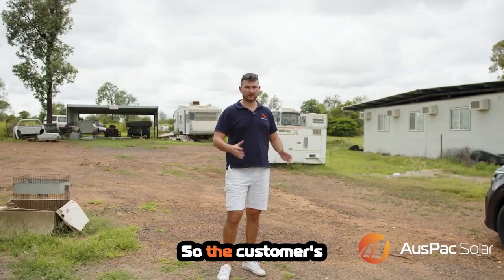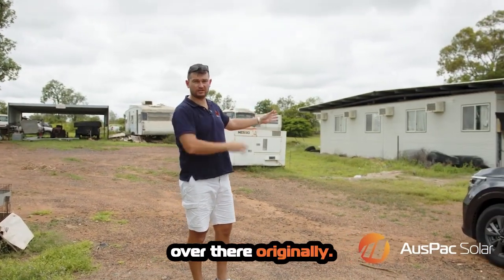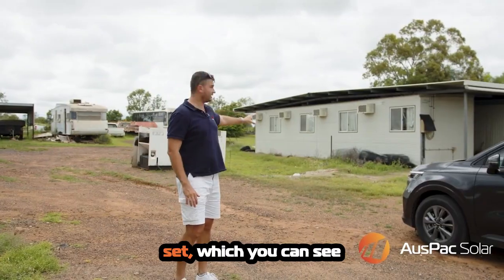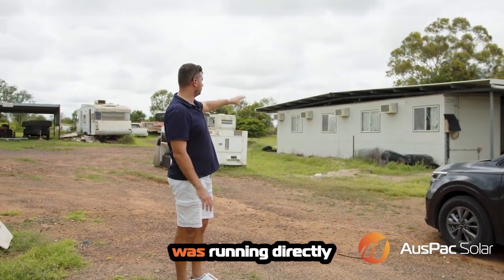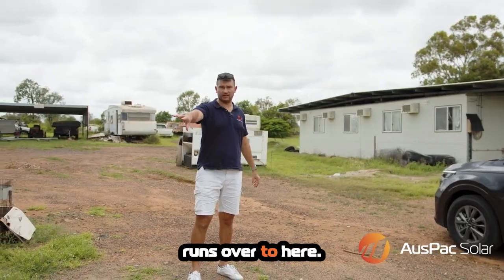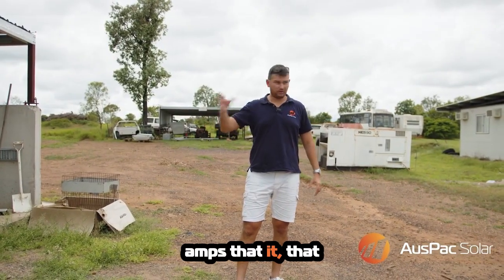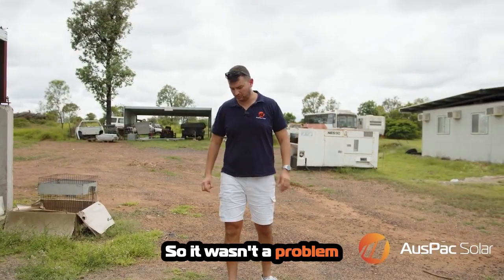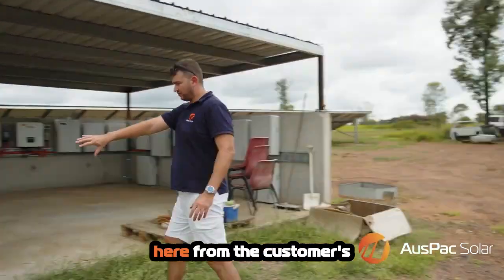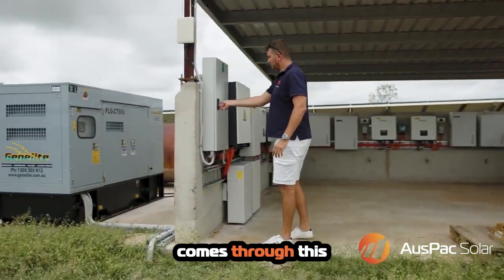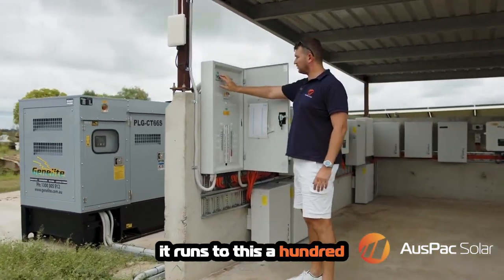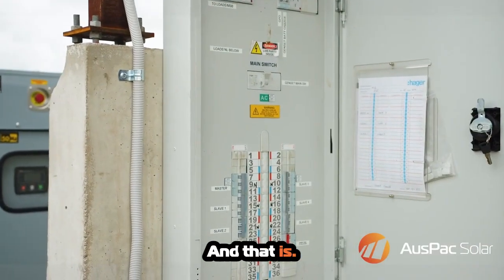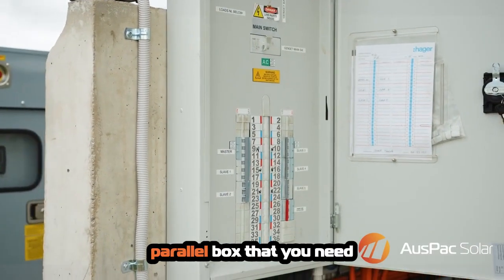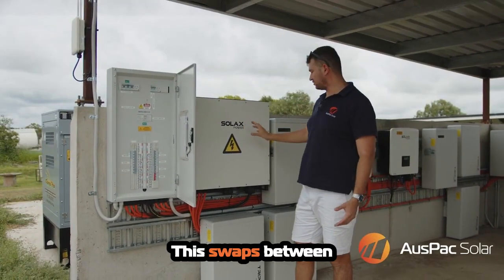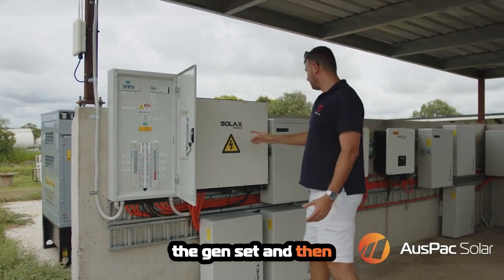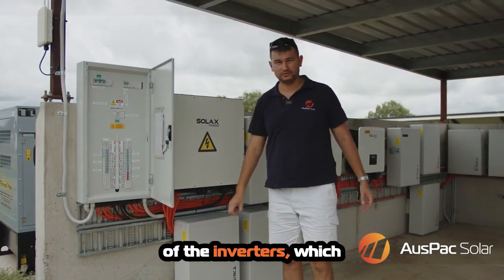so that the battery stays charged to start up the genset. So the customer's main switchboard is over there. Originally, that is what the generator, the genset, which you can see behind me, and that the customer had arranged, was running directly to. That cable actually runs over to here, but nonetheless, we're capped at 100 amps that the site is receiving, so it wasn't a problem with the size of the cable. So the cable comes up here from the customer's main switchboard and comes to this switchboard here. In this switchboard, it runs to this 100 amp three-phase breaker, and that is fed from this Solax parallel box that you need to purchase from Solax. This swaps between the genset and then the off-grid terminals of the inverters, which we'll go through shortly.